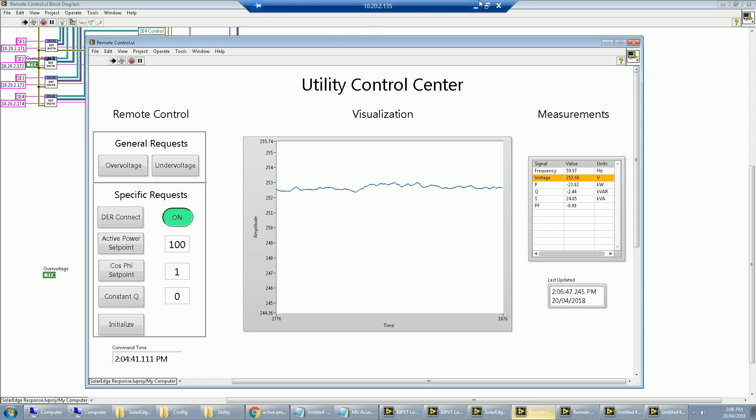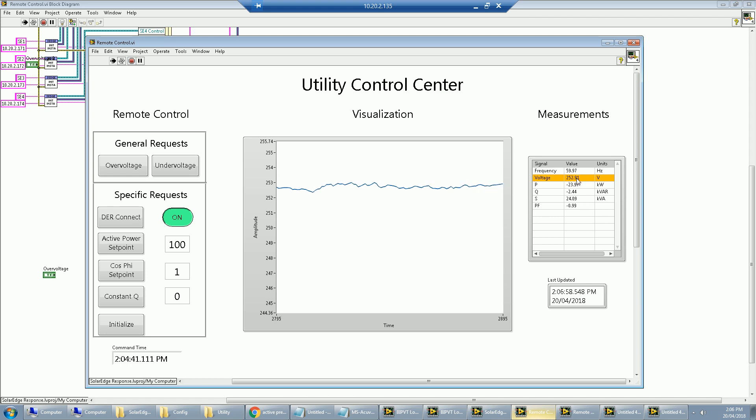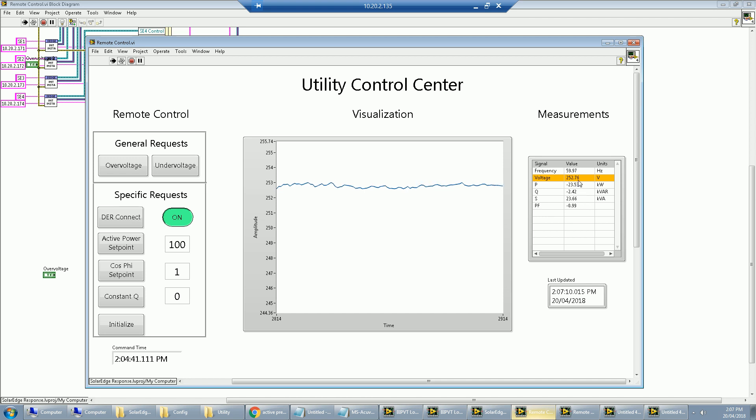We see the front panel here of this LabVIEW developed application, measurements and visualization in real time. We do see that the voltage here is definitely above the 252 volt mark, which is the absolute maximum that you're allowed to operate at. And this value here, negative 23 indicates that we're exporting about 24 kilowatts or 23 kilowatts back to the grid.